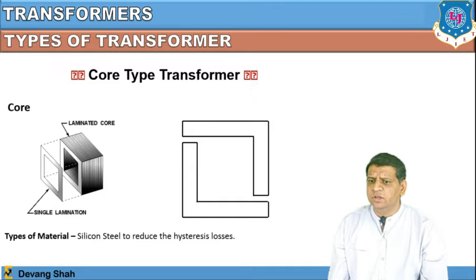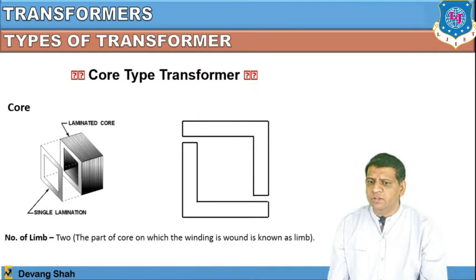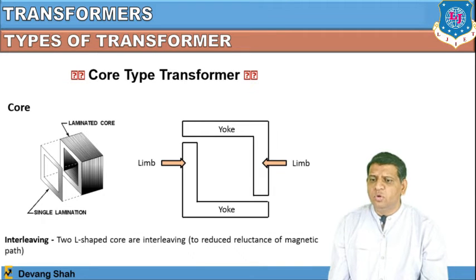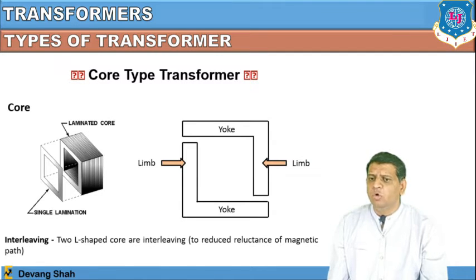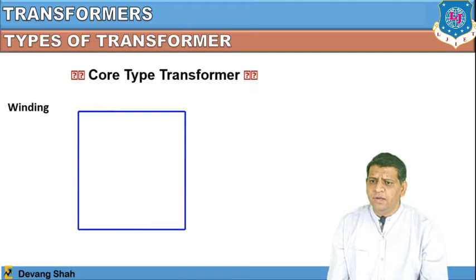The core is made of silicon steel to reduce hysteresis loss, and is square and laminated to reduce eddy current loss. There are two limbs — the part of the core on which the winding is wound — and two yokes — the part of the core that joins the two limbs. Two L-shaped core sections are interleaved to reduce the reluctance of the magnetic path, and multiple stampings are connected together to construct the core.